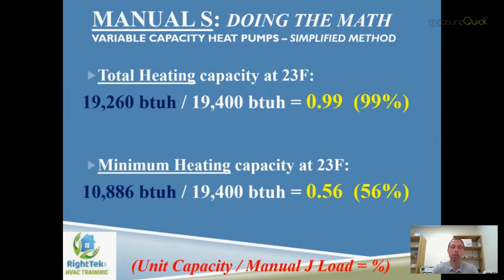So what we're trying to do here is make sure that the system stays loaded. It's ramped up where it spends most of its operating range hours, if you will, loaded up where it's in the upper percentage range of what it's allowed to ramp up and down to. We don't want it so oversized that it spends the bulk of its time running down at minimum capacity, because then we run into not only dehumidification issues in the summer months, but we also run into scenarios where we have oil return problems because of the lower RPM of the compressor. We're not getting a good oil return back to the compressor. And that, of course, can lead to compressor failures and things that we want to obviously avoid out there.